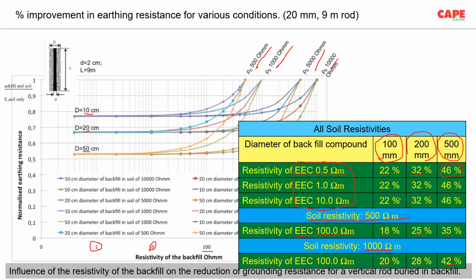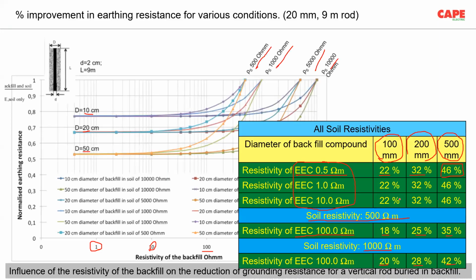So if you fill up this earth enhancing compound at a dia of 100 millimeter, the improvement in the RE value is something about 20-22%, 18 to 22%. That's all. Don't expect that without earth enhancing compound in normal soil I get 10 ohm, but the supplier says I have a magic compound, and if you put my magic compound, you will get 1 ohm. This is impractical or impossible. Even with a magic compound, in normal condition 10 ohm, the best you can get is about 8 ohms if you fill 100 millimeters, something like this.